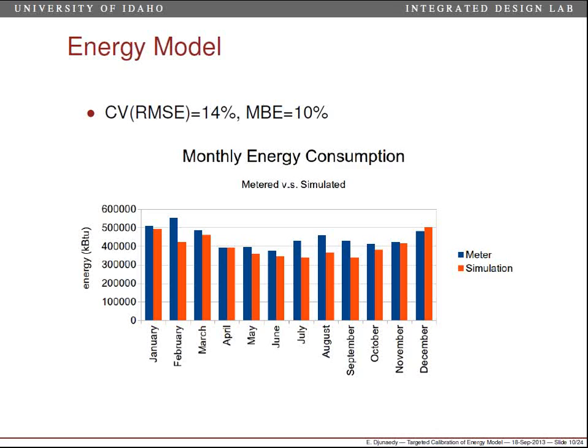I can't quite remember the exact criteria, but it's 15% for the CVRMSE, and the mean bias error, the MBE, is 10%. Our CVRMSE is 14% and MBE is 10%, so it is considered calibrated. Not bad for an as-designed model to be so close to the meter data.